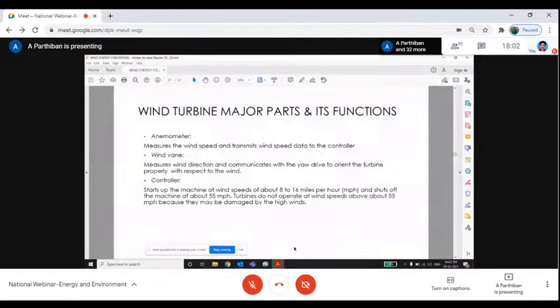And a lot of sensors are used: wind vane, anemometer, temperature sensors, vibration sensors. A lot of things are utilized, which I will go through in the further slides also. And another major thing is the control unit. There is a small control unit in the hub, another one in the nacelle, and a main control panel at the bottom of the tower. All three control panels are interconnected. All the data, whether sensor data or power data, is integrated. And from the main controller at the downside, through OFC it is taken to the SCADA. From there only, all the instructions will be given.